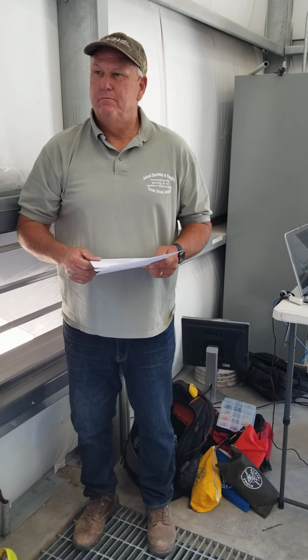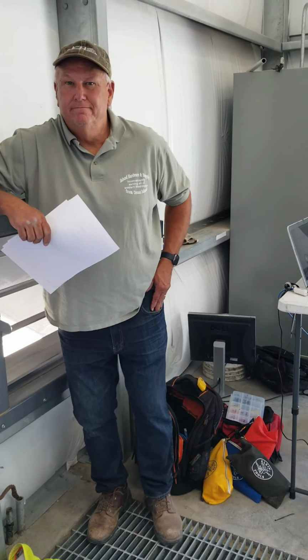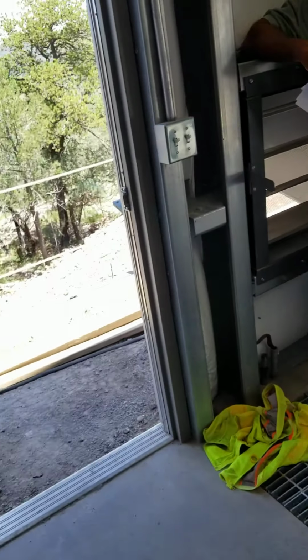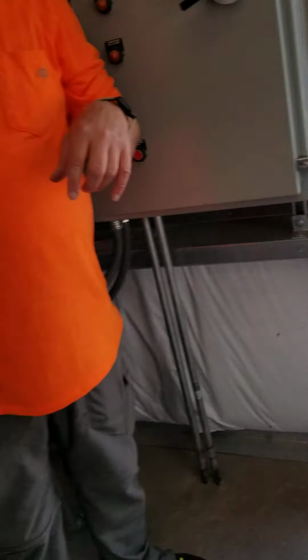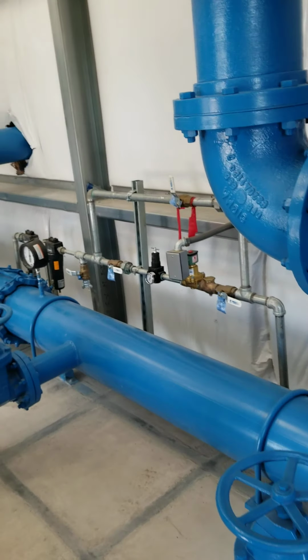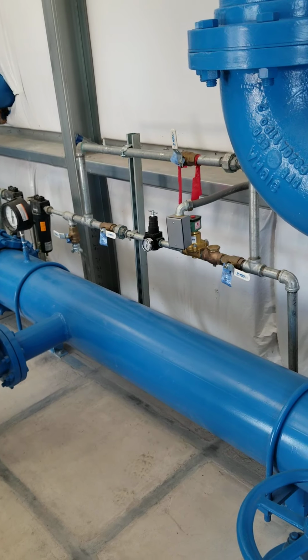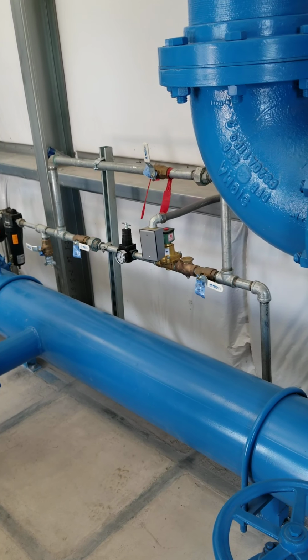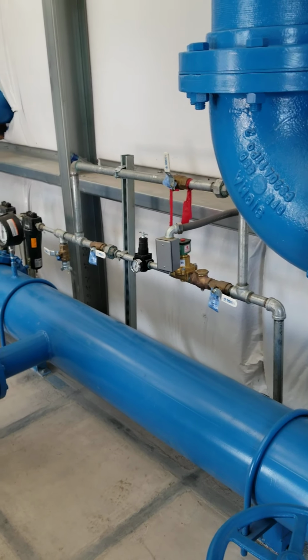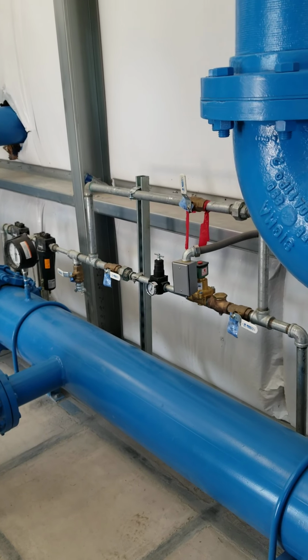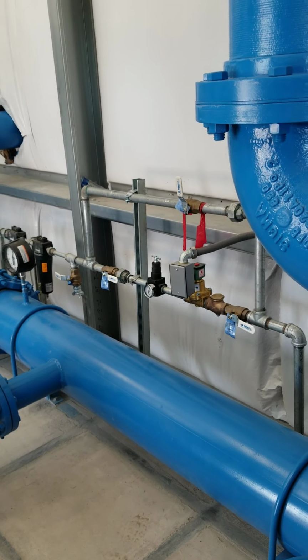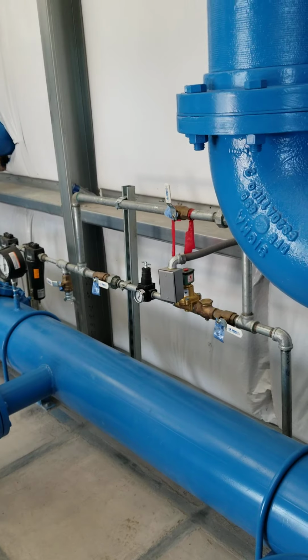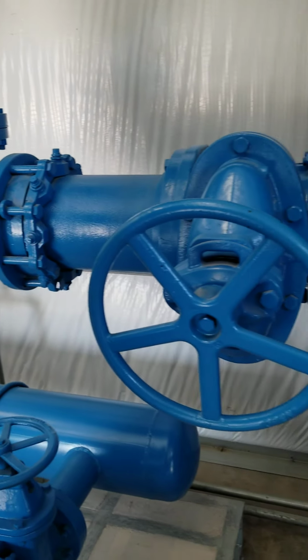To start the tank back up after you've taken it out of service, you're going to put the water level up to where the add air is, that mark on there, and then you're just going to open up your solenoid valve for adding air, and I should have pointed that out, is over here in this piping. There's a bypass ball valve at the top of it. Open that bypass ball valve and pressurize the tank up to 185, which is the pump shut off, and then you're back operational.